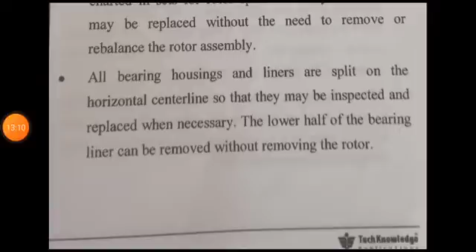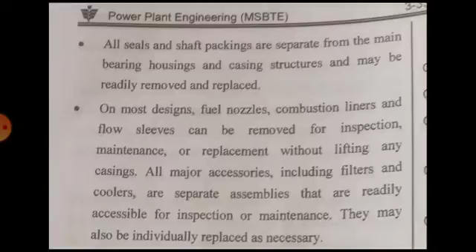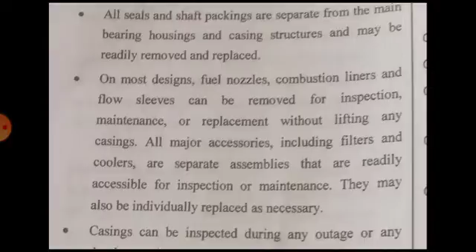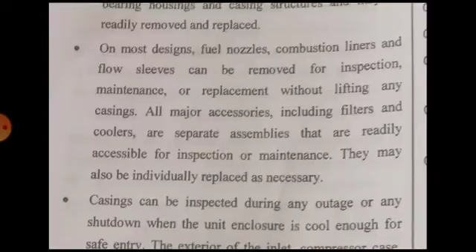Okay, then all seals and shaft packings are separated from the main bearing housing and casing structure and may be readily removed and replaced on most designs. Fuel nozzles, combustion liners, and flow sleeves can be removed for inspection, maintenance, or replacement without lifting any casing. All major accessories, including filters and coolers, are separate assemblies that are readily accessible for inspection or maintenance. They may also be individually replaced as necessary.